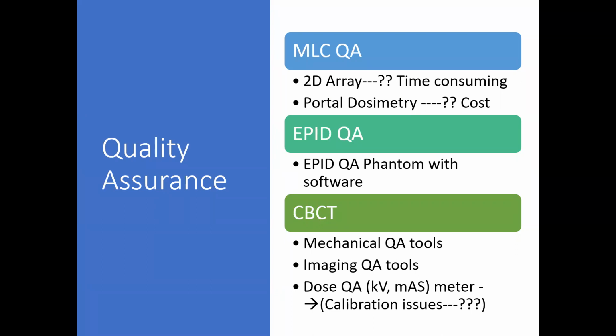It's from the same vendor. No literature at the moment says that you cannot use a system for the QA from the same vendor. Yes, there has always been an instinct about QA being done on a device from the same vendor, but there's no recommendation that you cannot use it. So I would suggest that in a setup like ours, where we have fewer colleagues in physics and a lot of work to do, even the treatments are being done on Saturdays and weekends on the machines, and we have less time to do our QA work on the equipment. So if we have a choice, we should ease our life by doing the portal dosimetry. Otherwise, if I buy a 2D array, I have the finances and have purchased a 2D array, it will take me so long that I will end up not doing QAs. So make your life easy and make decisions amongst different things as per your need.